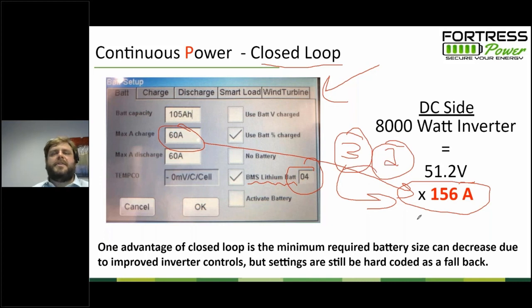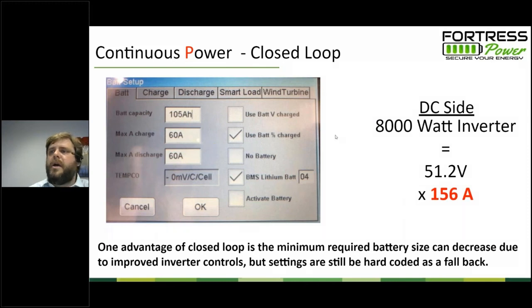If you're trying to design a system with the least amount of storage capacity possible, which implies the least project cost possible, selecting a closed loop inverter with one of our batteries can diminish the minimum battery size. Right now Sol-Ark with the eFlex is what we're furthest ahead on. So if you're used to installing 3 eflexes with an 8 kilowatt battery inverter, from time to time check up on our status of closed loop, because you might find that the smallest warrantable battery for your design has shrunk as we get more closed loop communication online.